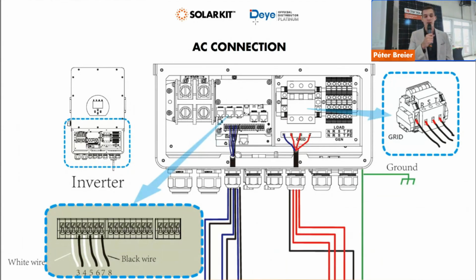There is one little mistake in the user manual, because you can see three phases connected here and the neutral line, but the PE is also here on the right side. You can see, from the circuit breaker on the right side, an additional rail. There you have to connect the PE. That's very important, because if you don't connect that, the inverter will not start up. And you have the load and the generator port, and we have another colleague here who will present after me, and he will introduce the use cases of these two ports.